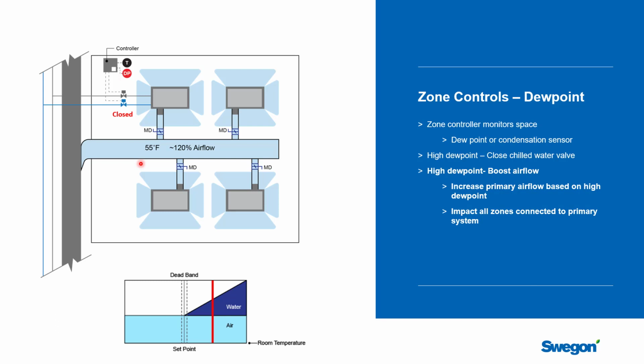So there's a couple of reasons that helps you. The first one is, remember that it's the primary air that is the drying source in the building. Its dew point was picked out of the air handling unit based on the design conditions of the building. So the more of that air you get to the space, the faster you're going to dry it out. And the other thing is, it's actually very hard to keep humidity trapped in one zone. I mean, we're only seeing one zone here, but if this was some kind of conference room, or they had open patio doors or allowed some way to get a lot of humidity in the space, that humidity will travel through this zone to the adjacent zones.